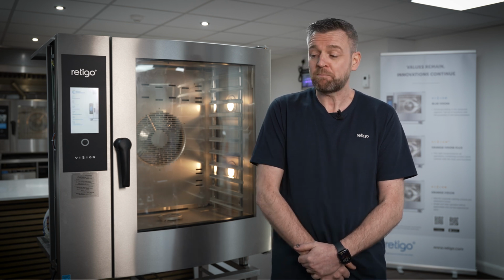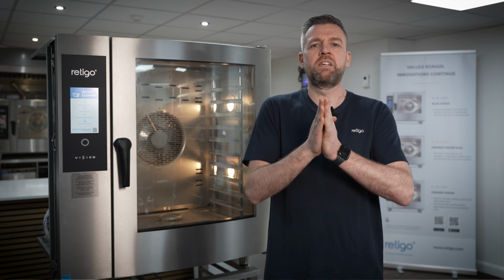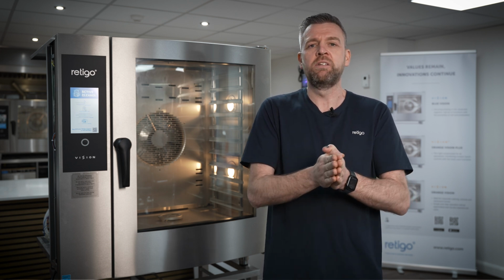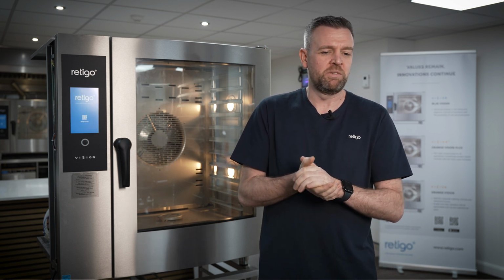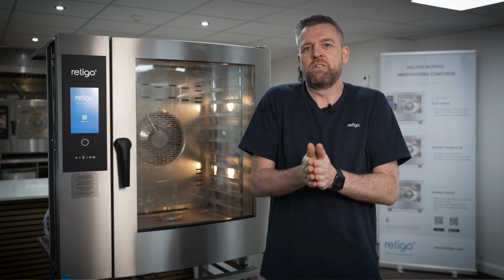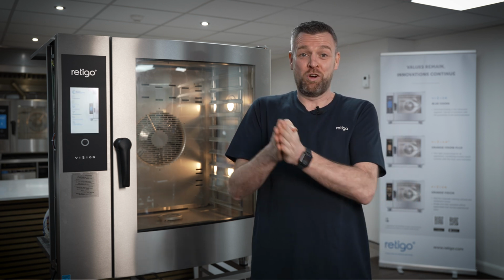important water treatment is. One thing about water treatment is, 100% categorically, it is way better, and it's the truth, to pre-soften than to descale after. There are ovens on the market which supply some descale tablets and say that that's fine. It's actually not, because it costs you more in energy to heat hard water than it does to heat soft water.